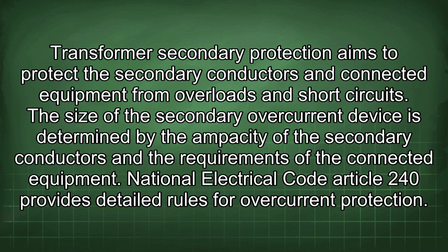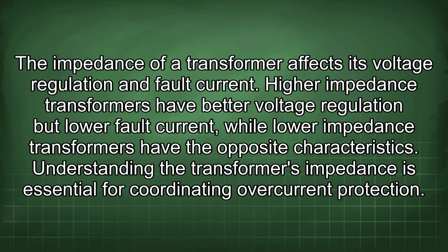Transformer secondary protection aims to protect the secondary conductors and connected equipment from overloads and short circuits. The size of the secondary overcurrent device is determined by the ampacity of the secondary conductors and the requirements of the connected equipment. National Electrical Code Article 240 provides detailed rules for overcurrent protection. The impedance of a transformer affects its voltage regulation and fault current. Higher impedance transformers have better voltage regulation but lower fault current, while lower impedance transformers have the opposite characteristics. Understanding the transformer's impedance is essential for coordinating overcurrent protection.